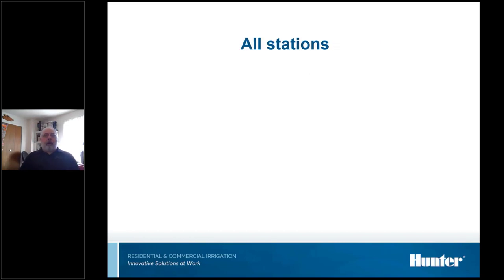Okay, so this is where things get interesting. Like I say, this is usually where I get involved on most troubleshooting two-wire situations. Nothing works. So what do you do? Where do you start? Well, you start at the controller. Check the controller. Reset the controller. A controller is a piece of electronics. It's a microprocessor. So just like your smartphone, just like your computers, sometimes they just need to be turned off. They get electrically confused and they just need to be reset.